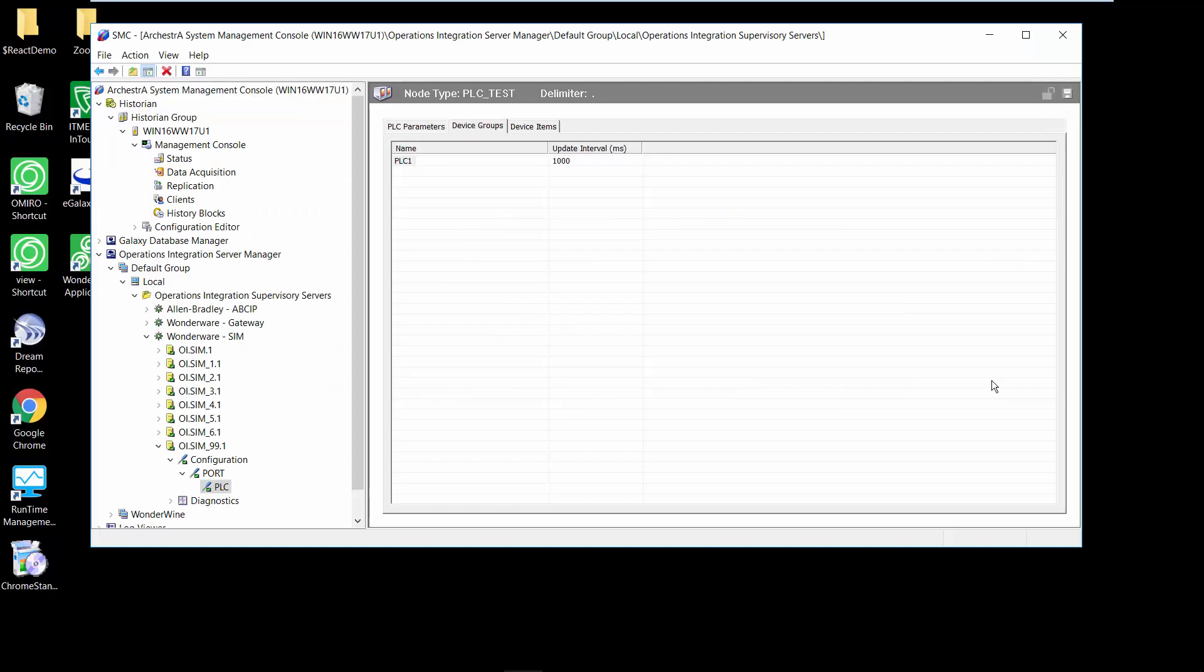So let's take a look at behind the scenes of how we're doing this. Every I/O server that Wonderware has or new OI servers that Wonderware has there is a device group and in the device group we have an update interval and that update interval was typically set at configuration time.